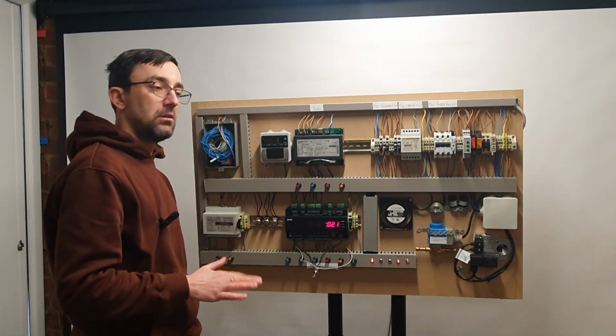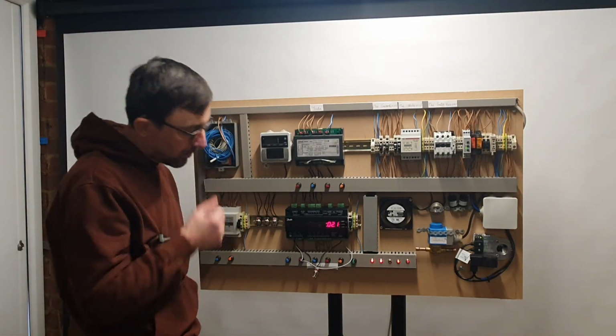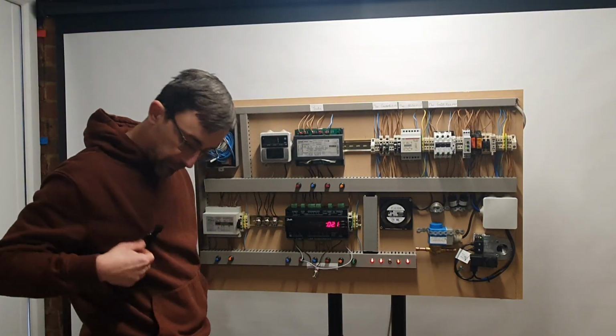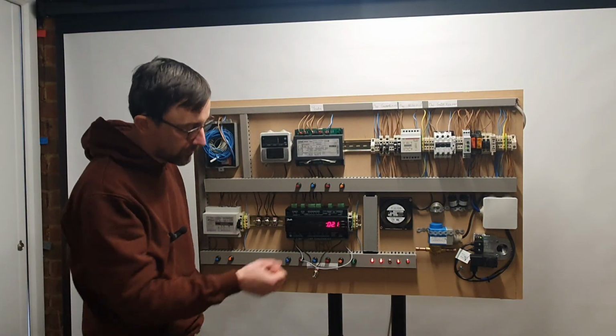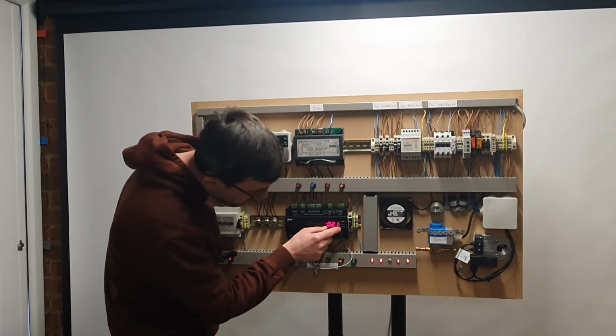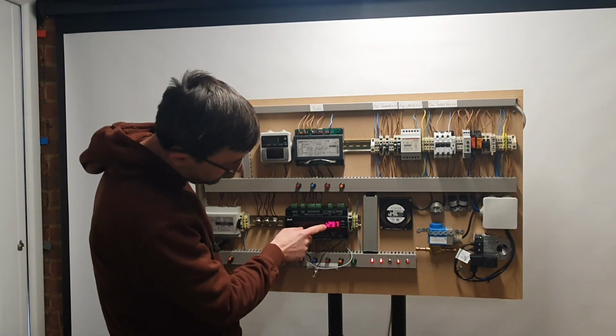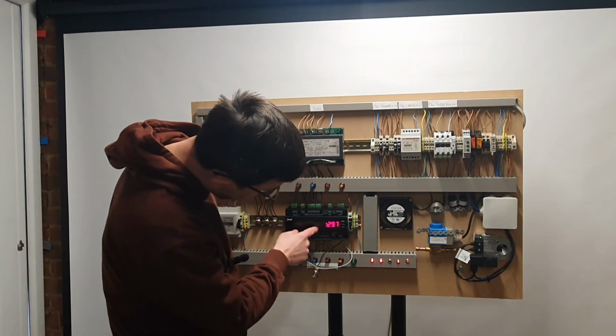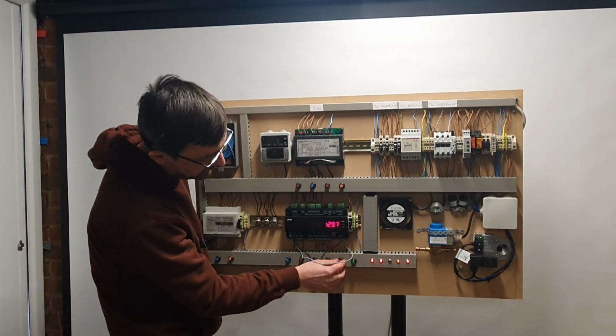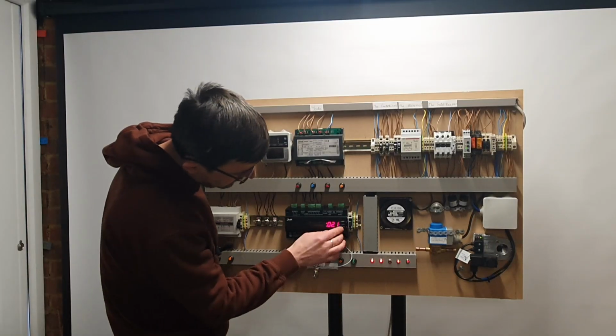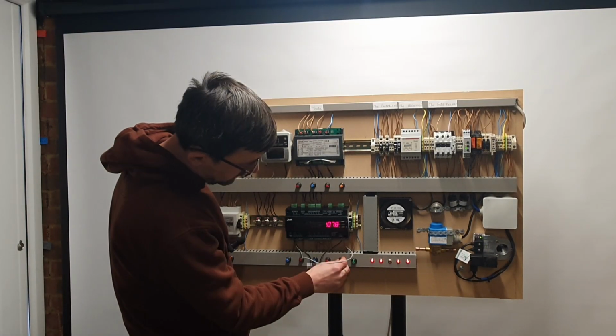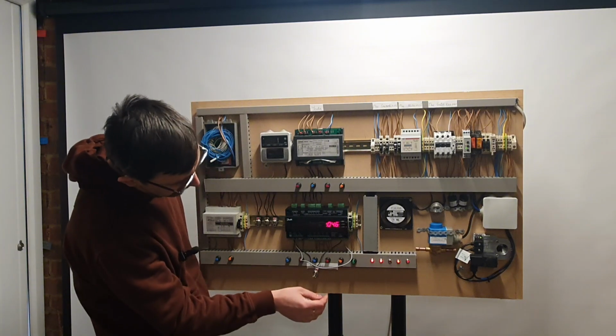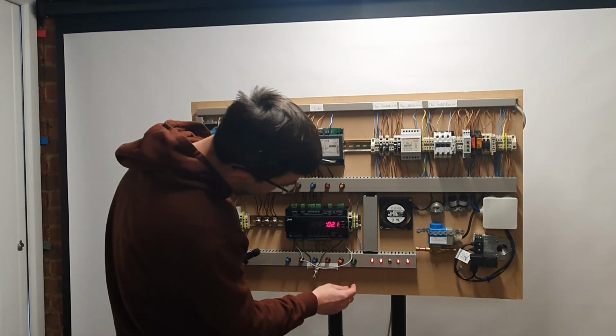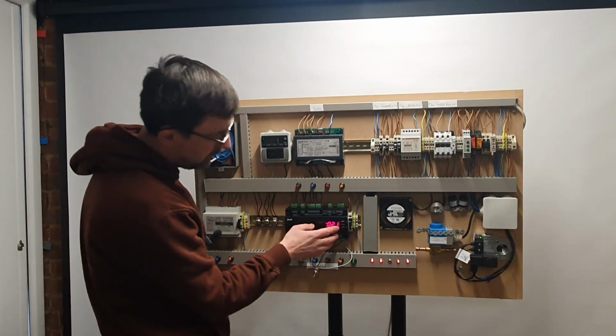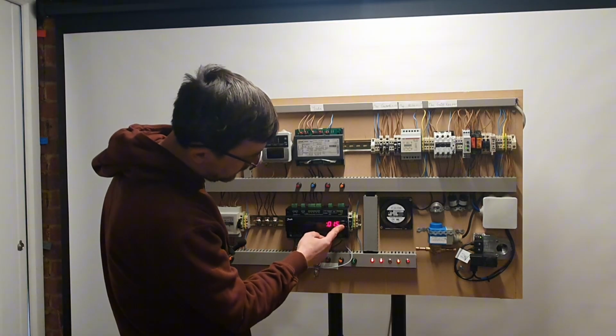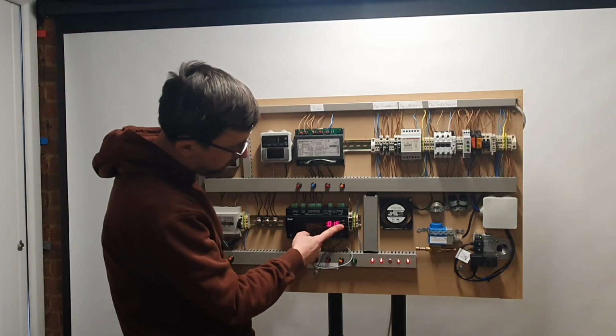Next thing, let's do a defrost test. I think the way to force this on defrost, let me just check. Yeah, the microphone is still working. I press this one. That gives me my defrost probe, which reads minus 29.7 degrees. Minus 4.2 degrees. Okay, so let's force it on defrost. Let's wait for it.